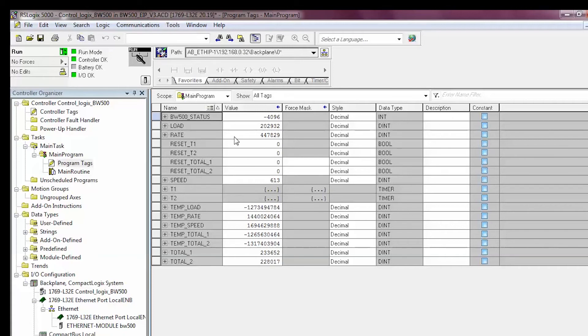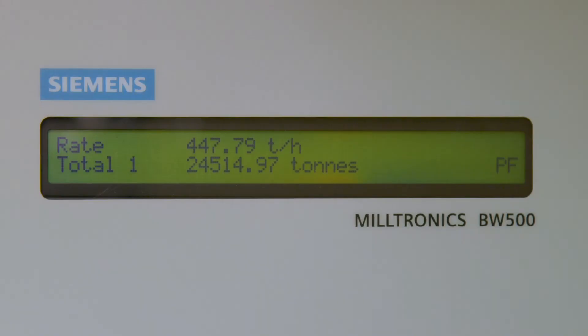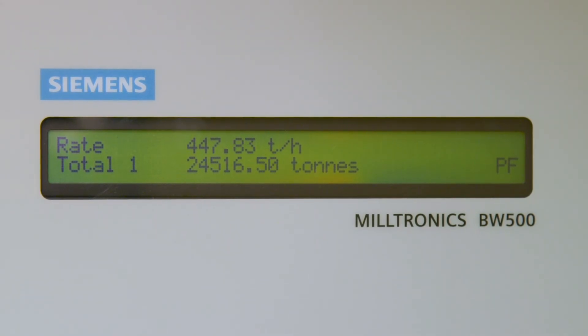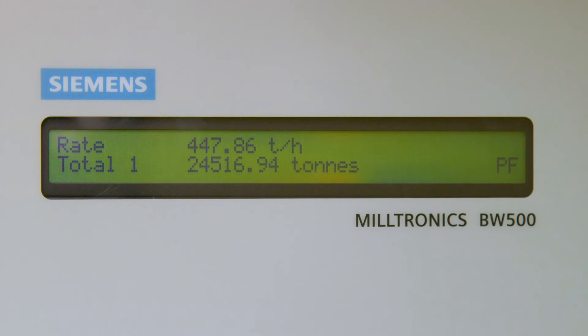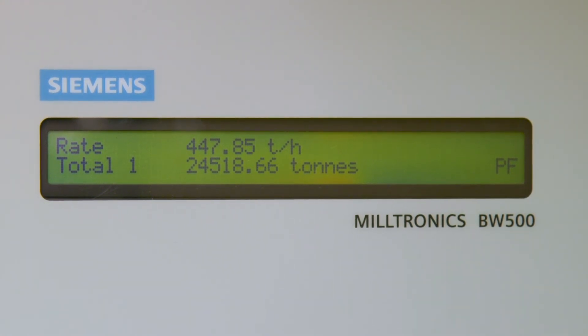Compare the process values to the BW500 display to confirm that everything is working correctly. Many processes will require the BW500 totalizers to be reset via communications. Ensure P799 on the BW500 is set to 1 for remote communications enabled.